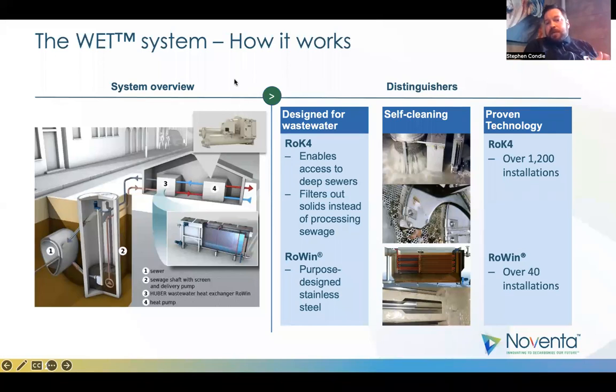So they've developed a carriage that goes across and mechanically scrapes the outside of the tubes in the tube bundle heat exchanger. Once all that cleaning happens, all the particulate that's been pumped into the heat exchanger, plus all the biofilm that builds up on the energy transfer surface area, it moves across the bottom of the heat exchanger with another screw. All of these motors are fractional horsepower motors and only run for a few minutes a day. Next slide.